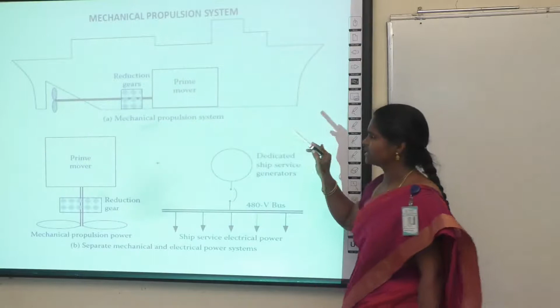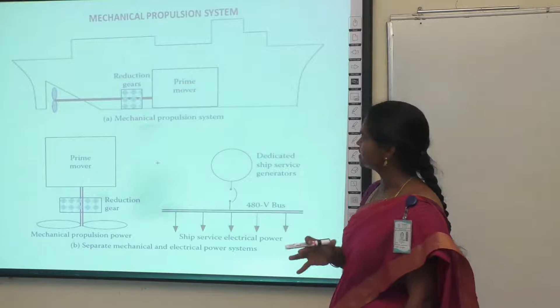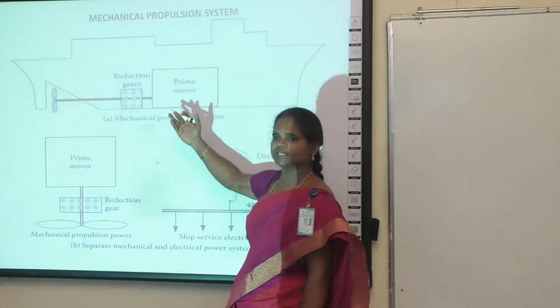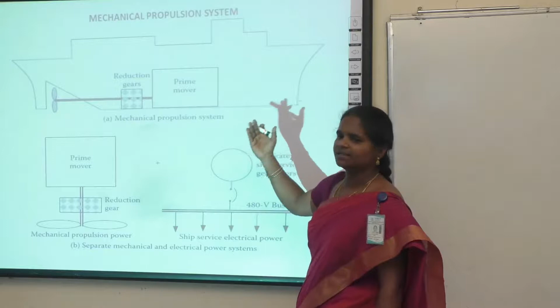Now these things are removed: the reduction gears, the long metal shaft, everything is removed in electric propulsion. Based on the power electronic converter, controlling the speed and driving the motor will be simple. This long shaft is nowadays replaced by cables. Just think of the maintenance of this shaft, removing the shaft and placing it again. Compared to this, cable maintenance is very simple and it can easily be replaced.